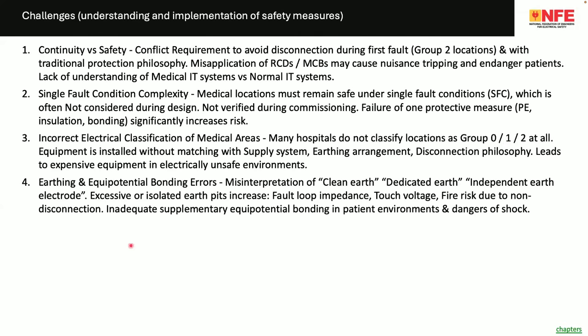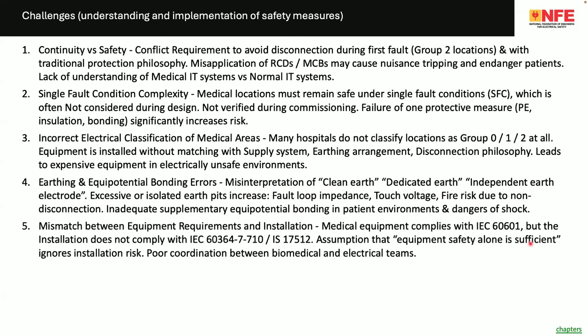Earthing and equipotential bonding errors: misinterpretation of clean earth, dedicated earth, independent earth electrodes, excessive or isolated earth pits that increase fault loop impedance. So this is also a disaster, I would say, in most of the hospitals.